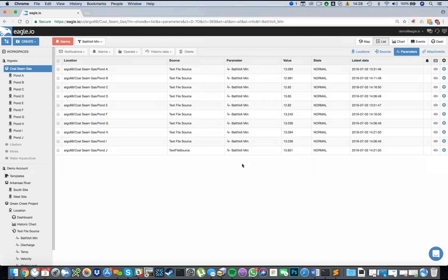Okay? We also have outdated alarms, meaning you can configure an alarm on a particular device. Now, look, if data hasn't arrived every hour, I want to be notified. So very quickly, when a site goes down, you can be notified by SMS or email and shown that attention is needed at that site if no data is arriving. Battery power, etc., might be the issue.